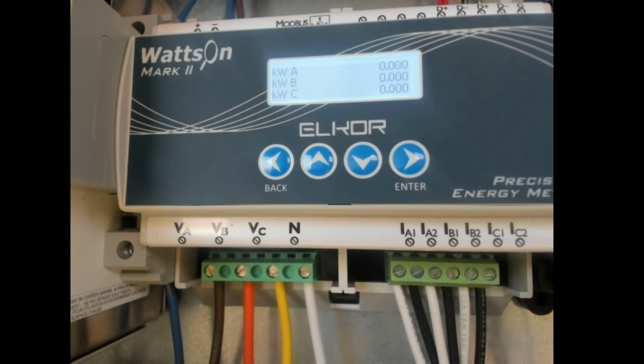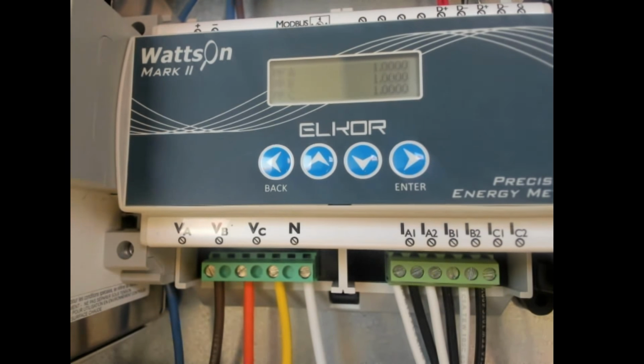Okay, because I've seen several projects in the 1 to below 5 megawatt range that are asking us to meter on 12 kV medium voltage lines. Okay. So typically I would start with the SEL 735. Yeah, I would start with the 735, but if there's a discussion about a lower cost option, the Elkor Wattson Mark II would work. Okay, got it, tabled. Thanks. Good question. Yep.